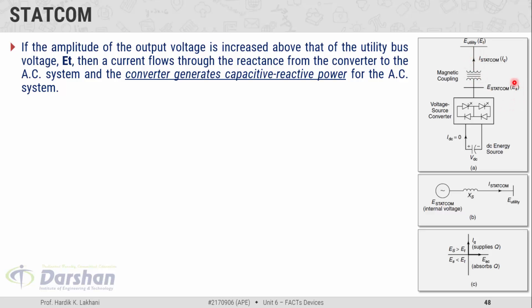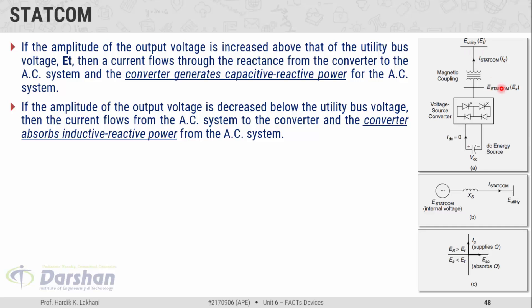When the magnitude of ES is greater than ET, the direction of the current is from the voltage source converter to the AC system. Conversely, when the magnitude of ES is less than ET, the STATCOM absorbs reactive power from the AC system. Hence, the magnitude of the output voltage of the voltage source converter decides the reactive power flow — whether the STATCOM should absorb or inject reactive power into the system.